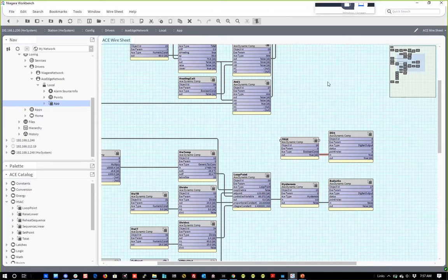Now you had the PCG controllers. You timed that as well. Yeah, the VAV ones were like 45 seconds or so because they had to go through the synchronization and all that stuff and then start up. Spiders were at like 15 to 20 seconds, I think, if I remember right. So they all take a little bit of time to come up and get running.